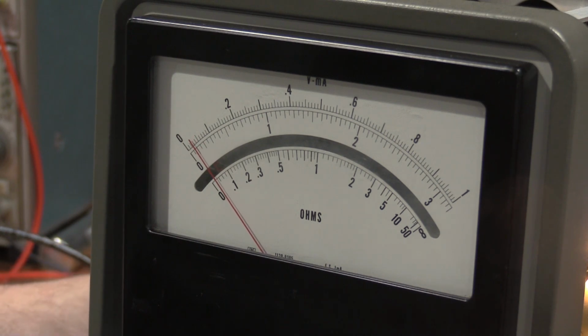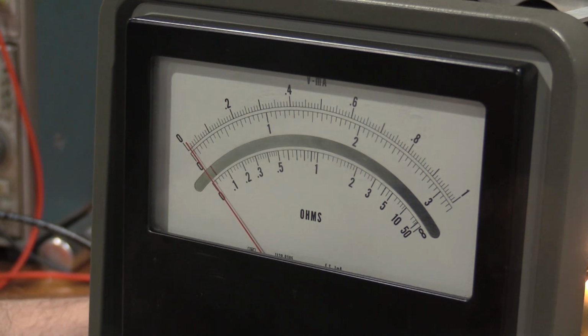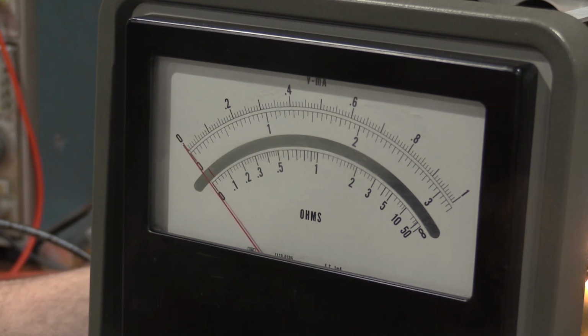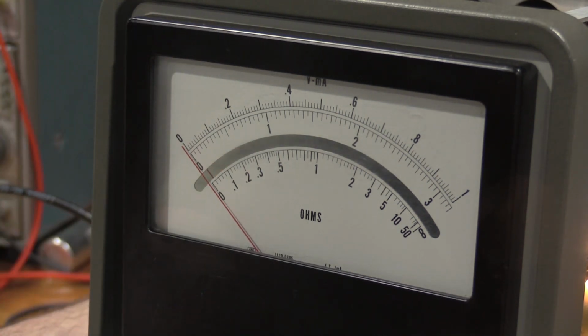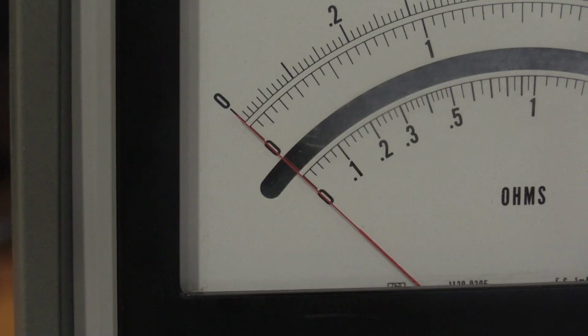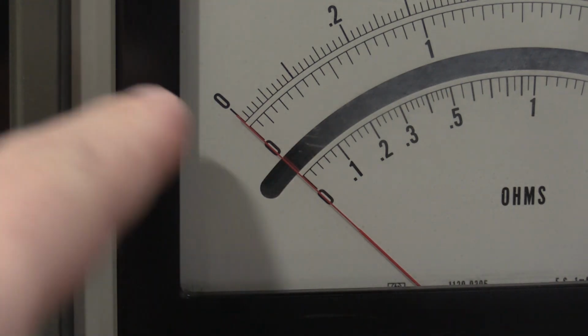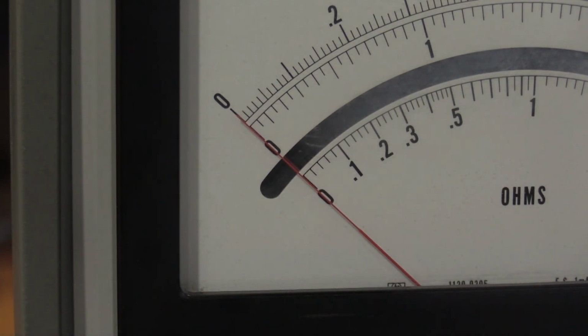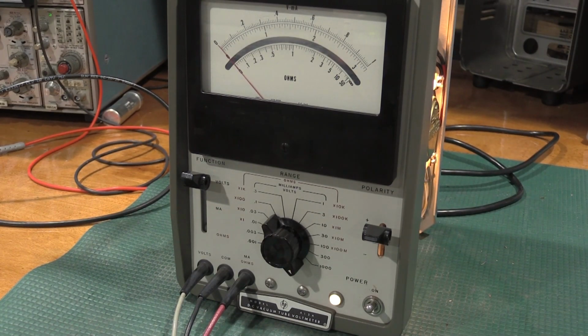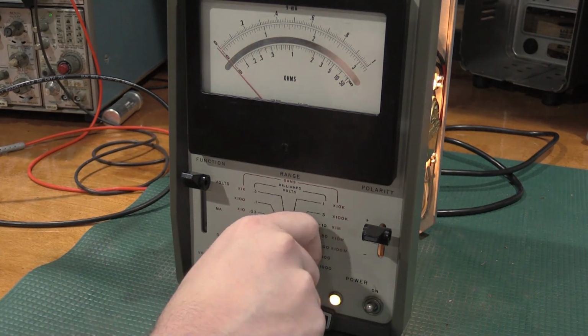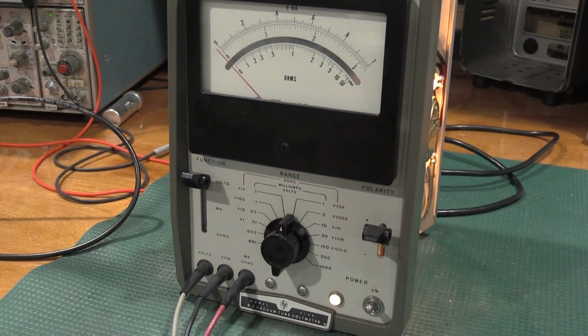So we want to bring this down. And this is a very, very touchy control. And it's also, because of the currents involved, a slow control to react when you get it close. And this is about as straight on as I can get the camera, but you can see we're dead lined up with 0. Okay, so on this one, the voltage calibration is done on the 1 volt setting. So what we want to do, crank this to 1. And now we're off a little bit.